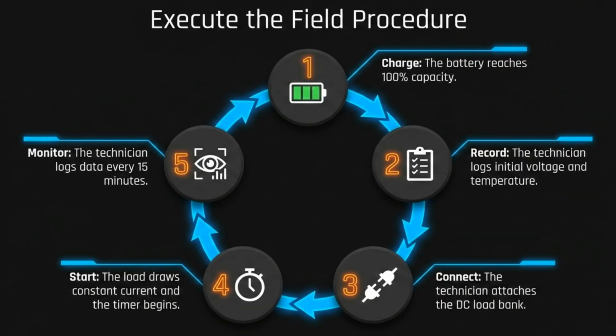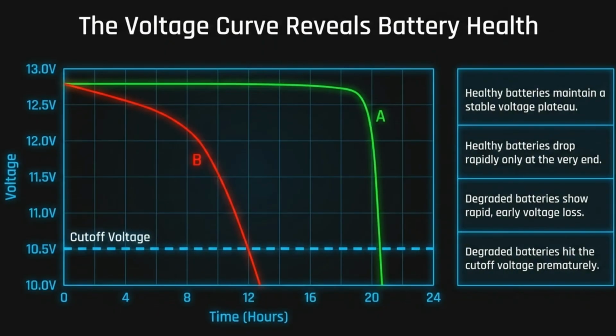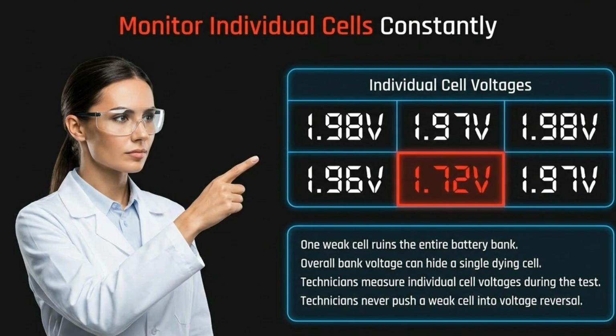Ensure the battery is fully charged, record initial readings, connect the load bank, start the constant current draw, and monitor the test every 15 minutes. The voltage curve is a key indicator of health. Healthy batteries maintain a stable plateau before a late drop, whereas degraded batteries show a rapid early decline toward the cutoff voltage. Monitor individual cell voltages throughout the process.